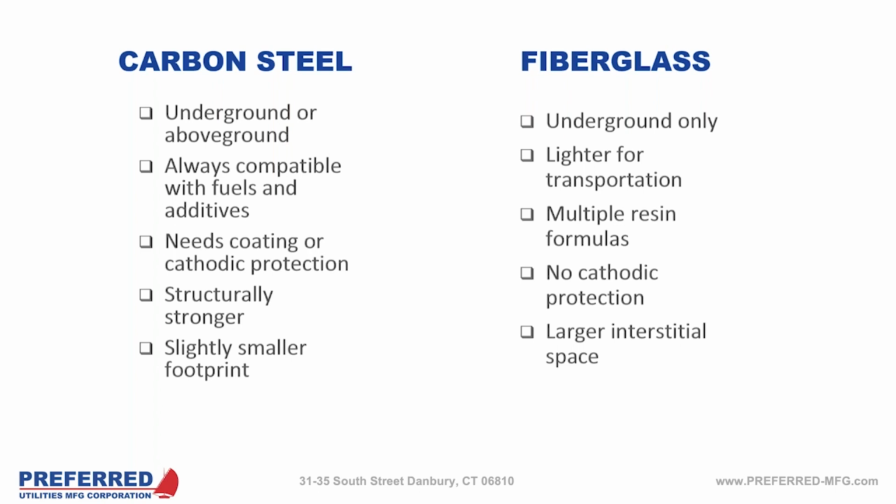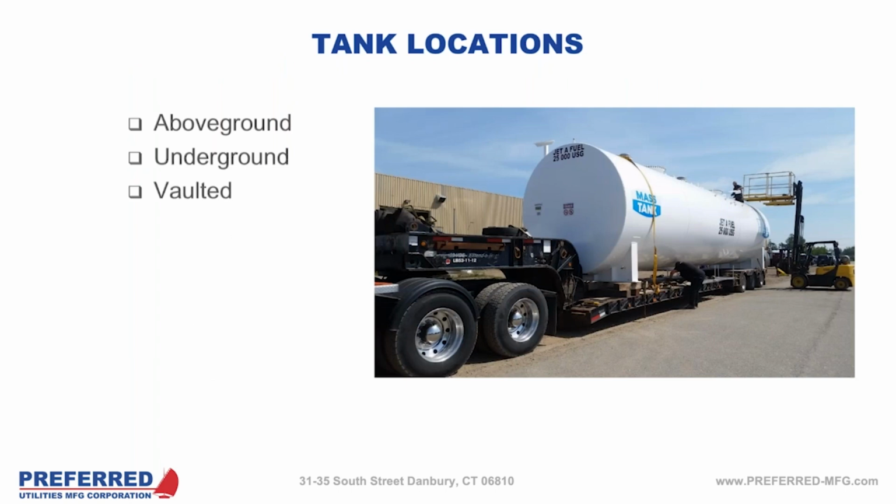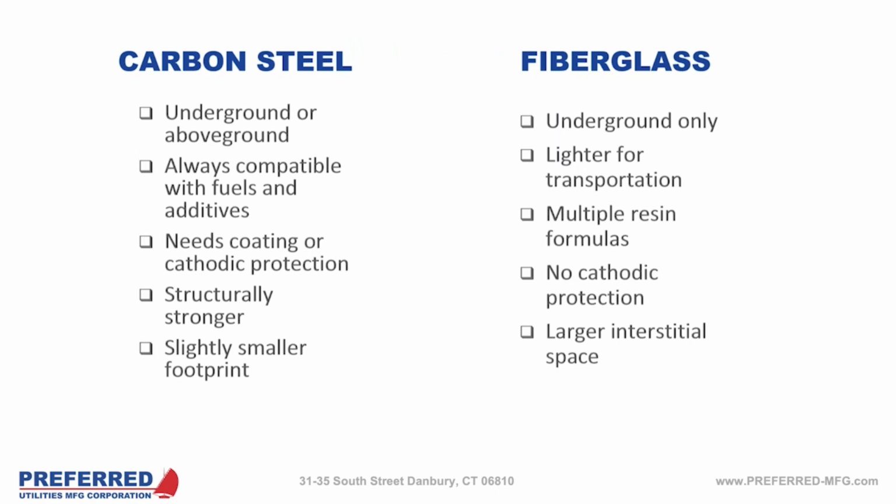But obviously, you don't need things like cathodic protection like you would on a steel tank. Adding in one other, Alex, you don't see them too often, but you also have your other fluids that you may be designing around as well. DEF, for instance, is huge. And the entire DEF system must be stainless steel. Otherwise, you'll get a lot of corrosion. So your main tank is stainless steel, your piping, your pumps, and everything is stainless steel.